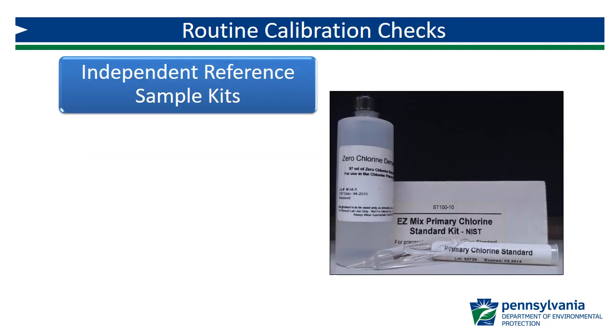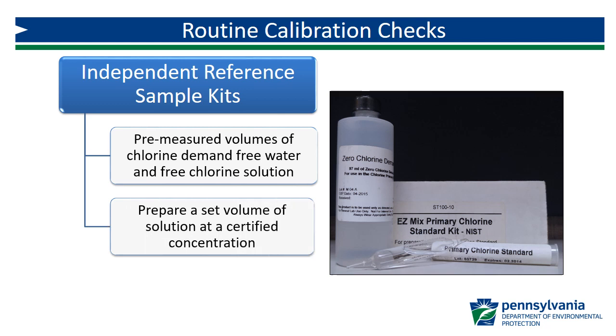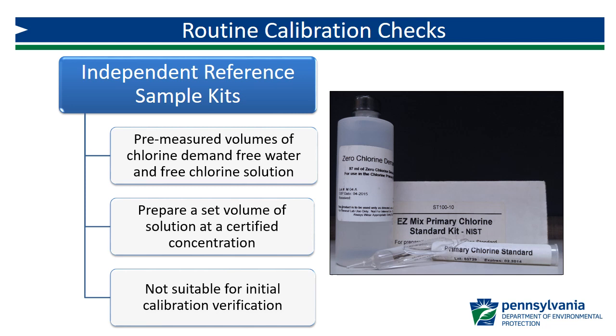Independent reference sample kits are an option available for routine calibration checks. These kits contain a bottle of pre-measured chlorine-demand-free water and an ampoule of NIST-traceable free chlorine solution. When mixed according to manufacturer's instructions, each kit produces a set volume of free chlorine solution at a concentration certified by the manufacturer. While they can be used for routine quarterly checks, they are not suitable for initial calibration verifications, as each kit only produces one concentration — and the initial calibration verification requires standards diluted to three different concentrations.